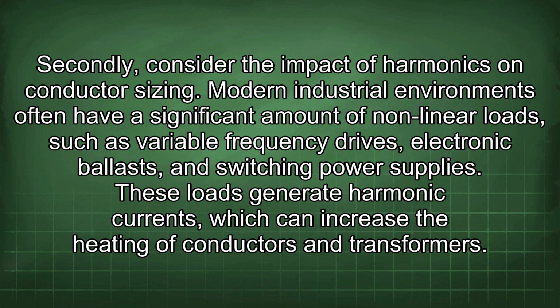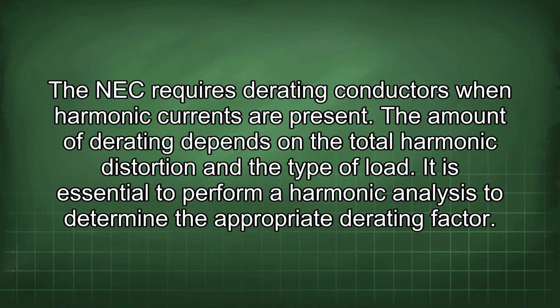Secondly, consider the impact of harmonics on conductor sizing. Modern industrial environments often have a significant amount of nonlinear loads such as variable frequency drives, electronic ballasts, and switching power supplies. These loads generate harmonic currents, which can increase the heating of conductors and transformers. The NEC requires derating conductors when harmonic currents are present.